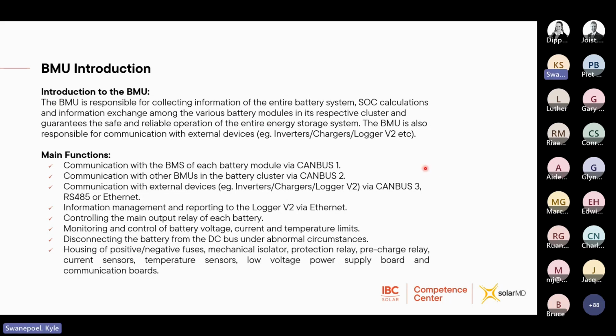Then the BMU, like I mentioned, is responsible for collecting all the information from all the modules. And then if you have multiple BMUs in your system, the BMUs share that information with each other. So this is responsible for collecting all of that information, calculating the state of charge, exchanging this information within that internal CAN bus on the BMU so that they can make a decision on charge and discharge parameters based on the whole battery bank and whether or not it is safe to operate. And then the BMU also does external communication with inverters or chargers or the Logger V2.